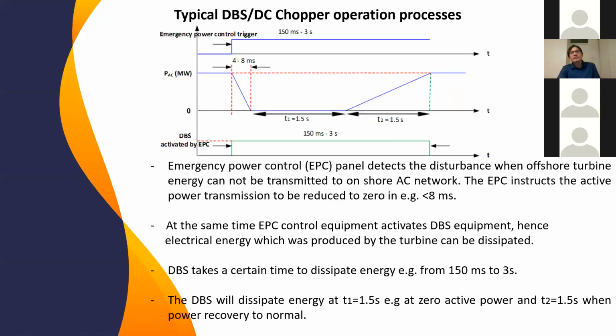How it works? When energy from the turbine cannot be delivered to the AC network, in case of any fault, for instance, the emergency control panel will instruct the station to stop the energy. So if before the fault the power may be transferred at 1 PU, EPC will instruct it to stop.